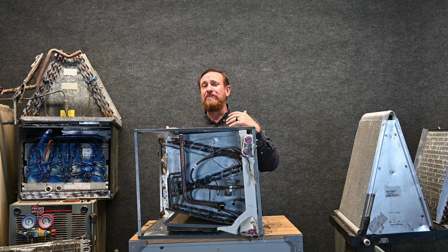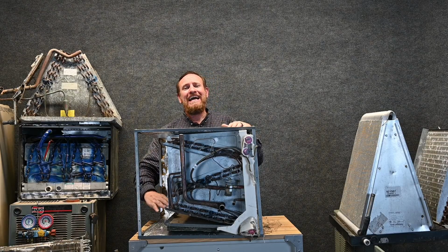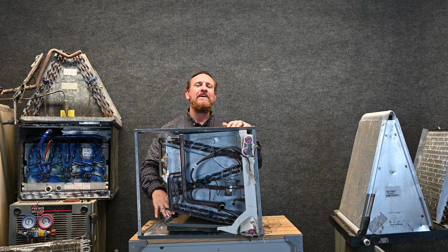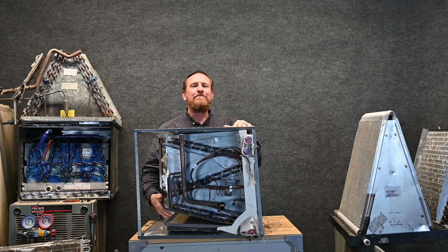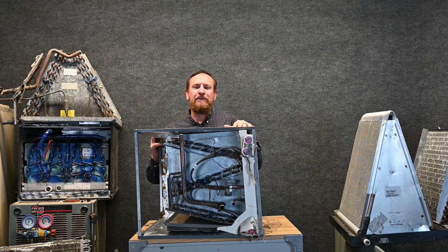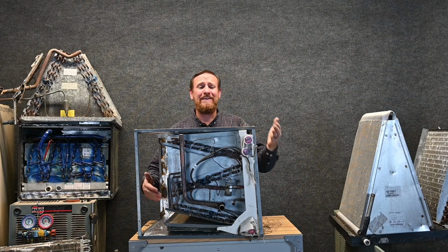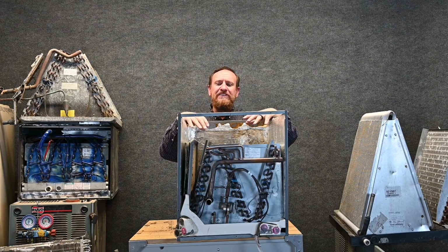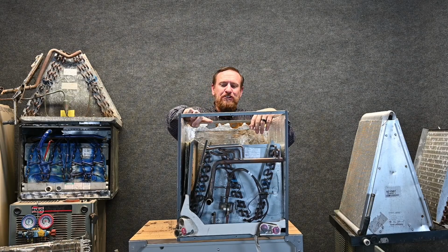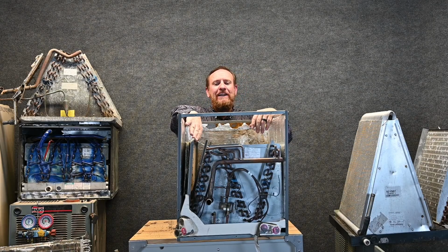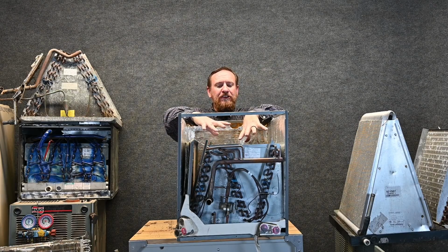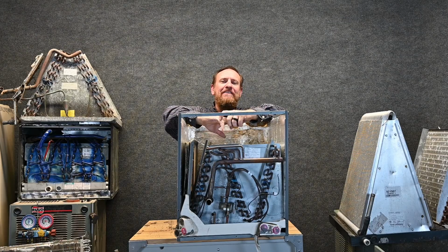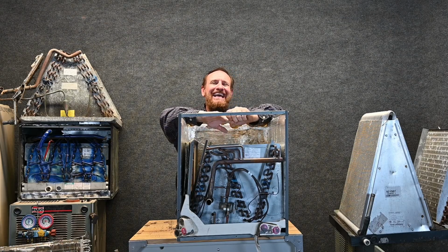Now personally, what I like to do is when it's an upflow system, I like to take this auxiliary drain pan out. A lot of people say it's too much work and that's going to be a case-by-case basis, but I like to have as many things out of the way that are not going to obstruct airflow as possible. So here I'm going to need that drain pan and this one as well. But if I have the coil sitting like this, and if it's not too much trouble, I will take this secondary coil out of the way so I don't have as much airflow restriction or airflow blockage. This coil is already going to reduce a lot of airflow as it is, and I want to make sure I have as least amount of other things causing problems as possible.